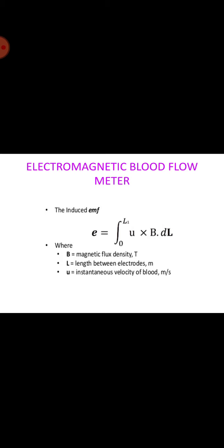Magnetic blood flow transducers are also manufactured as catheter tip transducers. For this type, the normal transducer design is essentially turned inside out, with the electromagnet located inside the catheter, which has the electrodes on the outside. The catheter transducers cannot be calibrated in flow units, however, because the cross-section of the blood vessel at the place of the measurement is not defined.